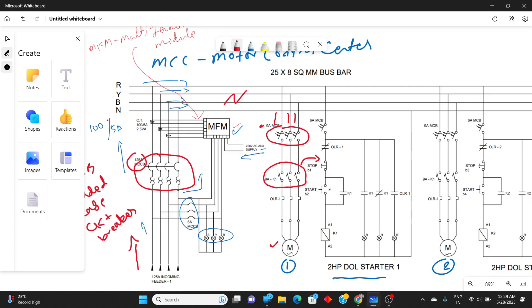Next we have the main contactor K1 contacts. To operate this we have a start button and a stop button. K1 latching contact is connected in parallel to the start button. This is the K1 contactor coil — any contactor coil is named A1 and A2. This is the control circuit, and the other part is the power circuit.